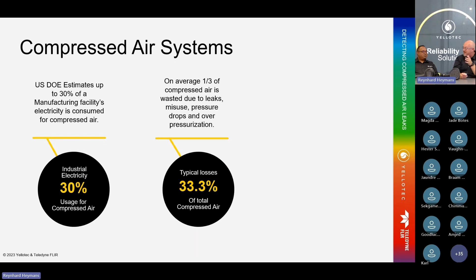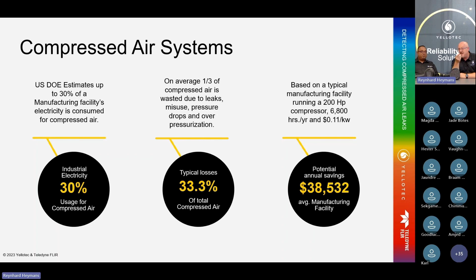If we take a simple example of a 200 horsepower motor, around about a 150 kilowatt compressor, working 6,800 hours per year at, let's say, 11 US cents per kilowatt hour, that's almost $40,000 that's being wasted. Yep. That $40,000 is already buying 2 units, if not 3.